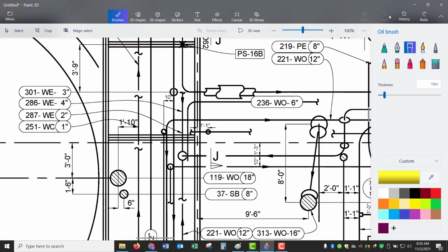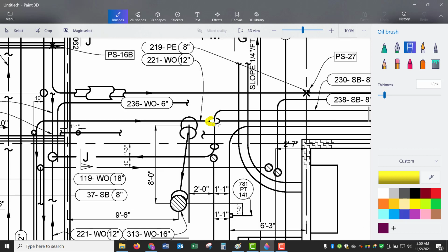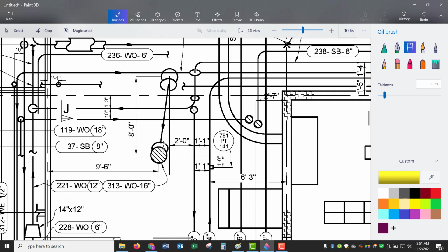In here we have some of these pipelines in circular shapes with section lines. Remember what those represent, that is coming straight towards us. If you see a circle that is like this interrupted by a line, then that means that that pipe at this point goes down. Some of those are not circles but elliptical shapes, so that means that this one here is coming from a higher area. It goes down at a 45-degree angle, typically 45 degrees, and then it comes down here and then continues that way. Some of these will have a different angle, like this one.